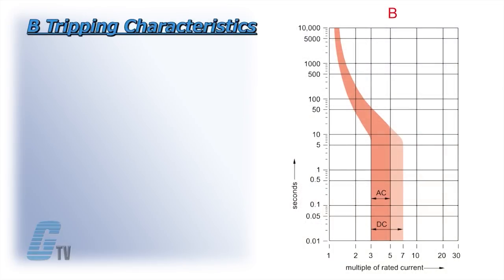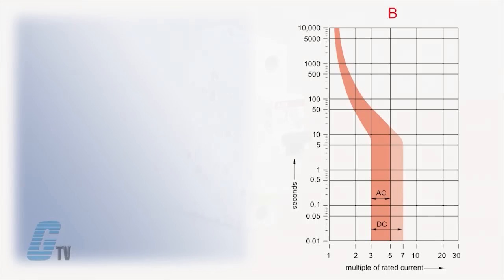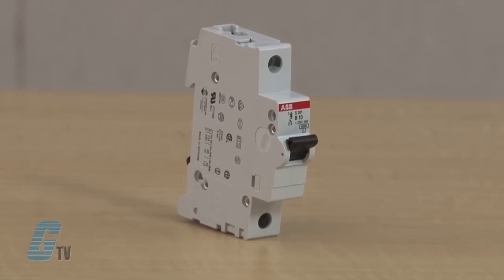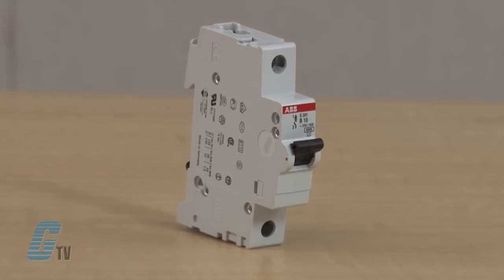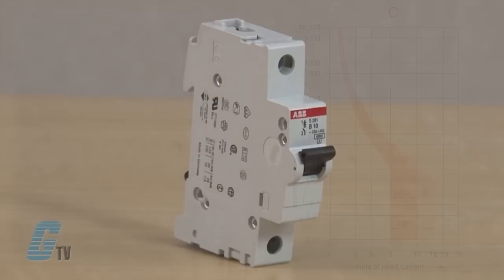The B tripping characteristics are available in breakers rated from 6 through 63 amps. The B time current curve is designed primarily for use in cable protection applications. Instantaneous tripping occurs between approximately 3 to 5 times rated current in 50 or 60 Hz systems. This quick trip curve maximizes protection of control circuits under low short circuit fault levels that could damage control wiring.